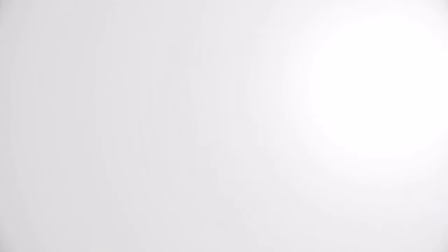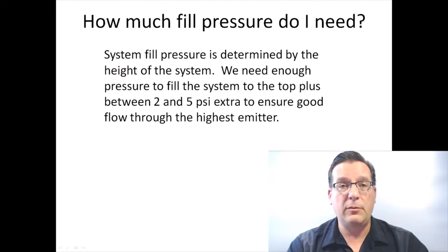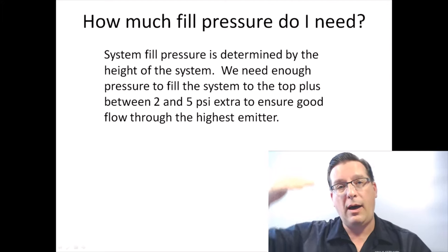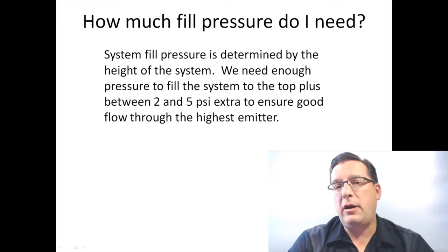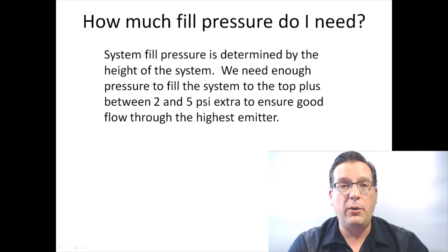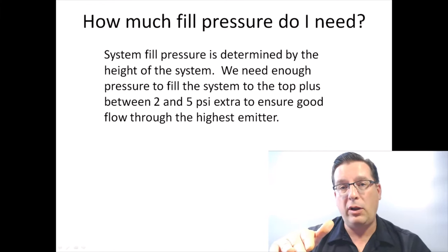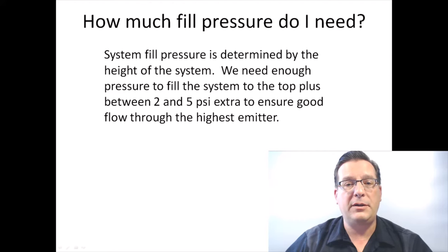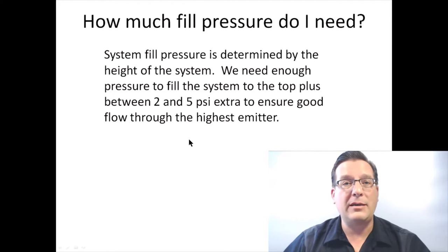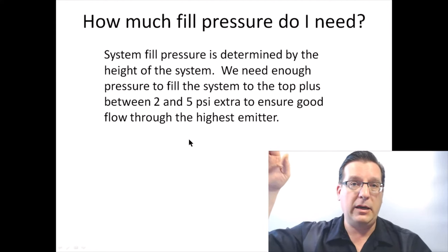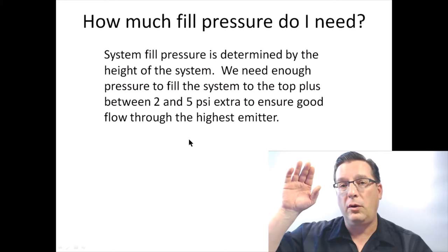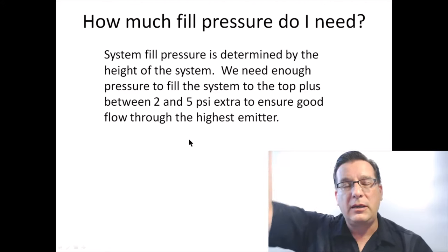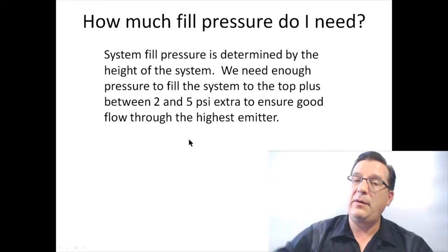The more difficult part is: how do I decide where to set the pressure reducing valve? On all hot water boiler systems, system fill pressure is determined by the height of the system — how tall is it, how high up in the air does that water go? Assuming the boiler is the lowest point of the system, in the basement, with all piping going up from there, we're going to need enough pressure to fill the system to the top plus an extra two to five PSI to ensure good flow through the highest emitter — the radiator, baseboard fin tube, fan coil, or whatever is at the highest point.